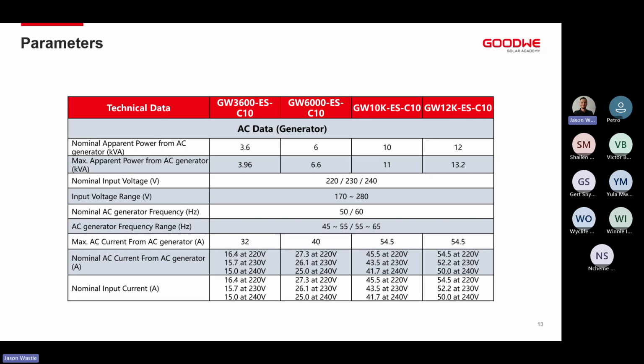Next, we'll have a look at the generator information. So our generator port is completely configurable, controllable, and we can set the generator's incoming voltages, incoming frequencies, prohibited working hours, and that kind of thing. And we can also set the generator's maximum capacity size and all of that as well.